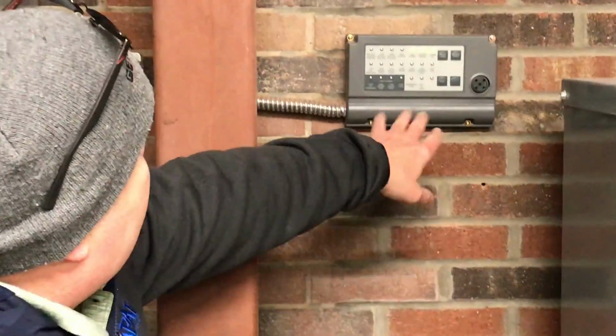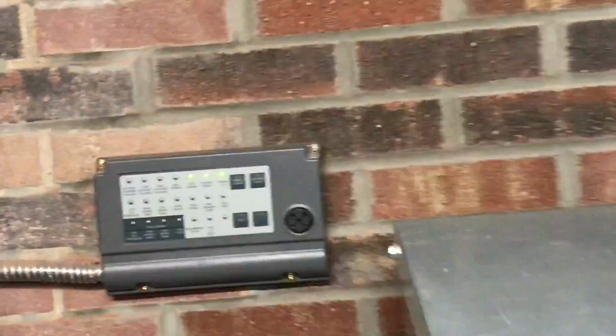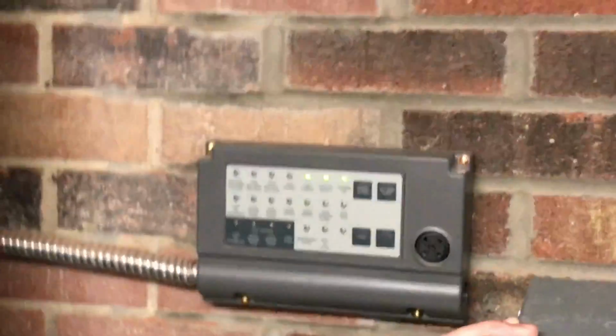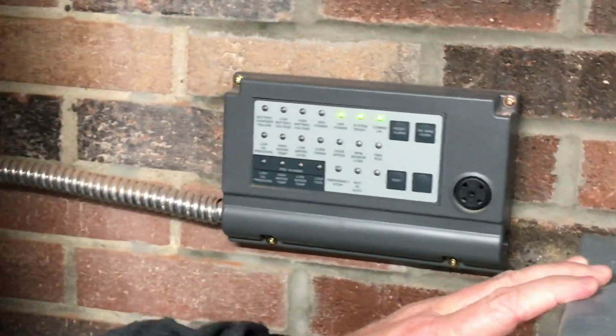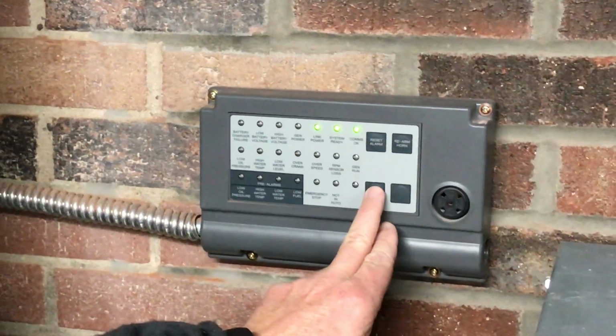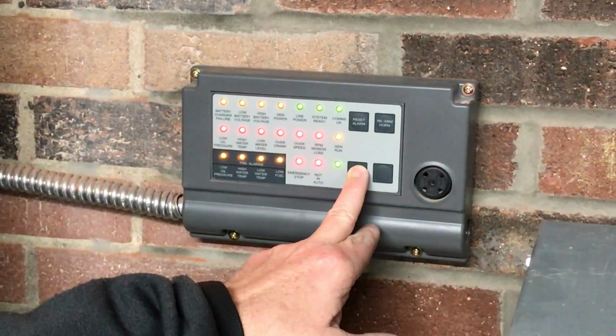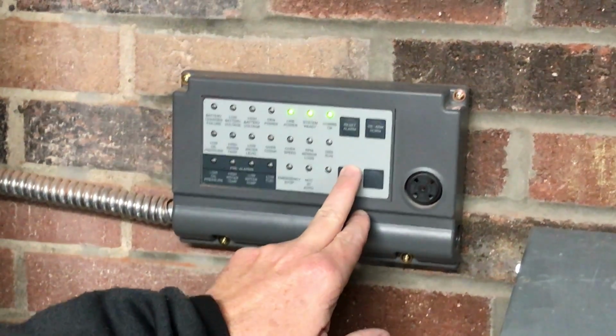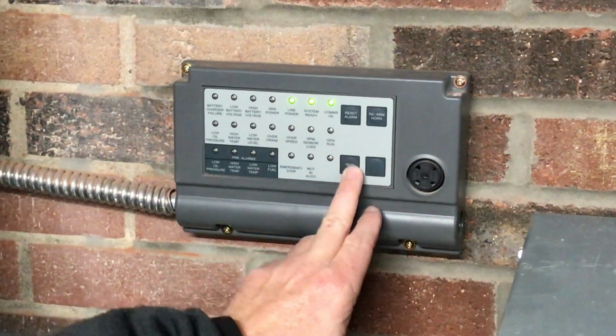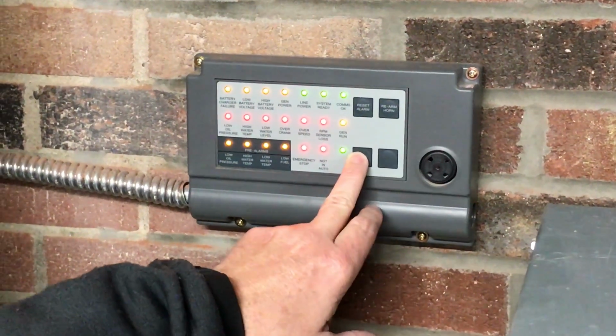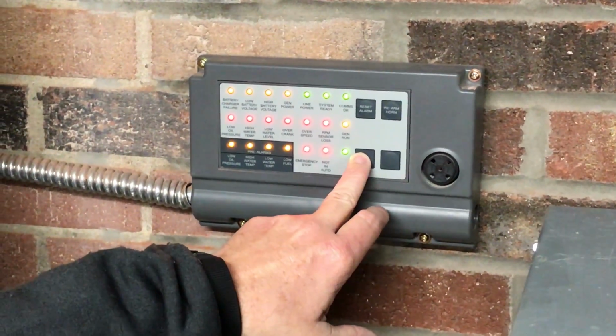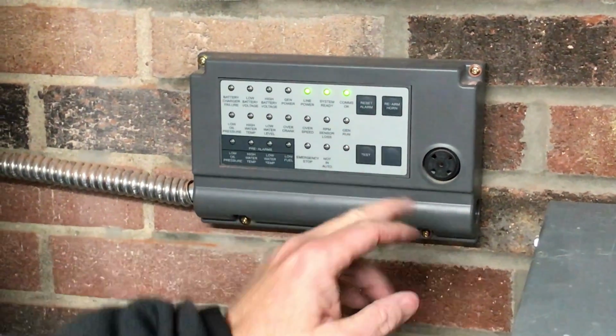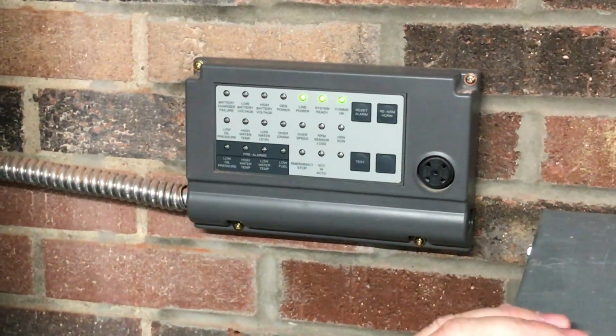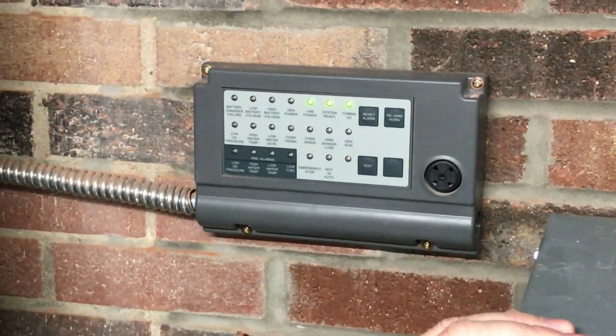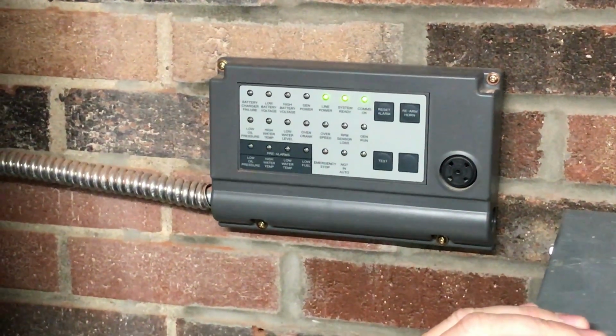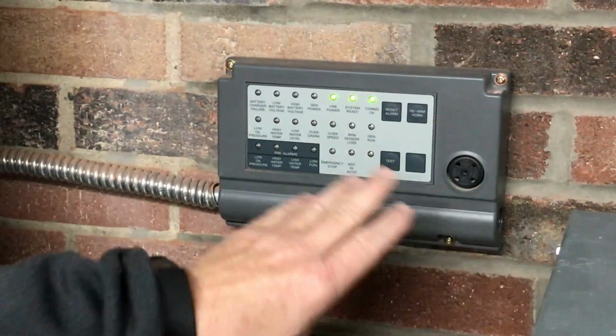Okay, so this is the remote annunciator. This is connected straight to the panel out at the generator. In the event that something is actually going on, that's what they're going to hear. Is there a lot of people in and out of this room? Okay, you can hear. So if there is an alarm going on, all they have to do is hit reset alarm, and that's going to acknowledge the alarm. It's not going to really reset anything until actually the event gets taken care of.